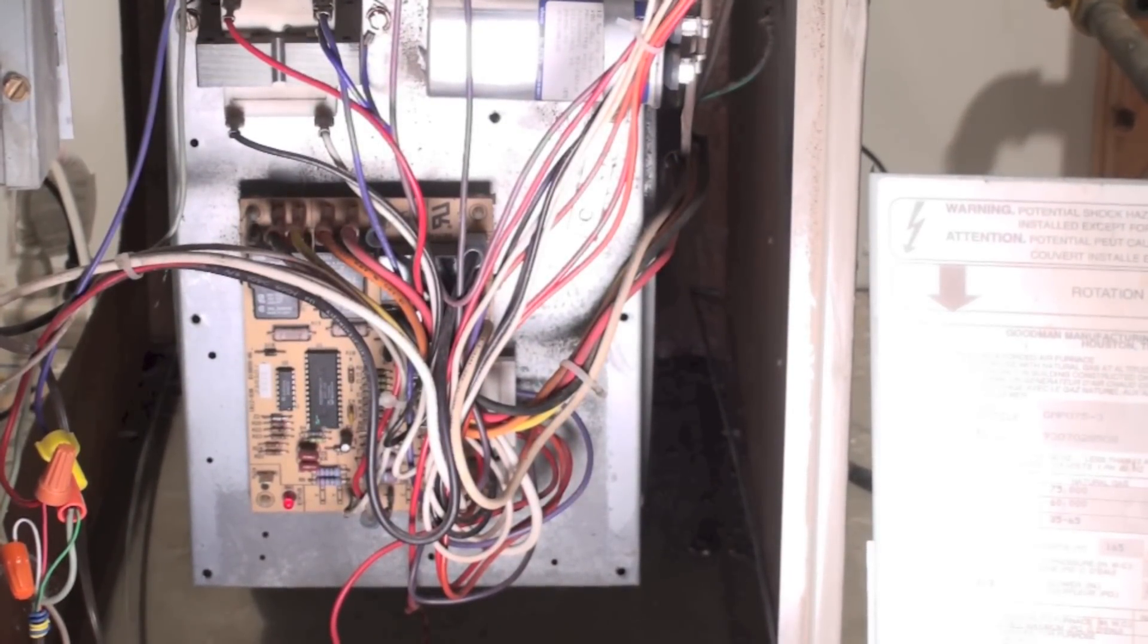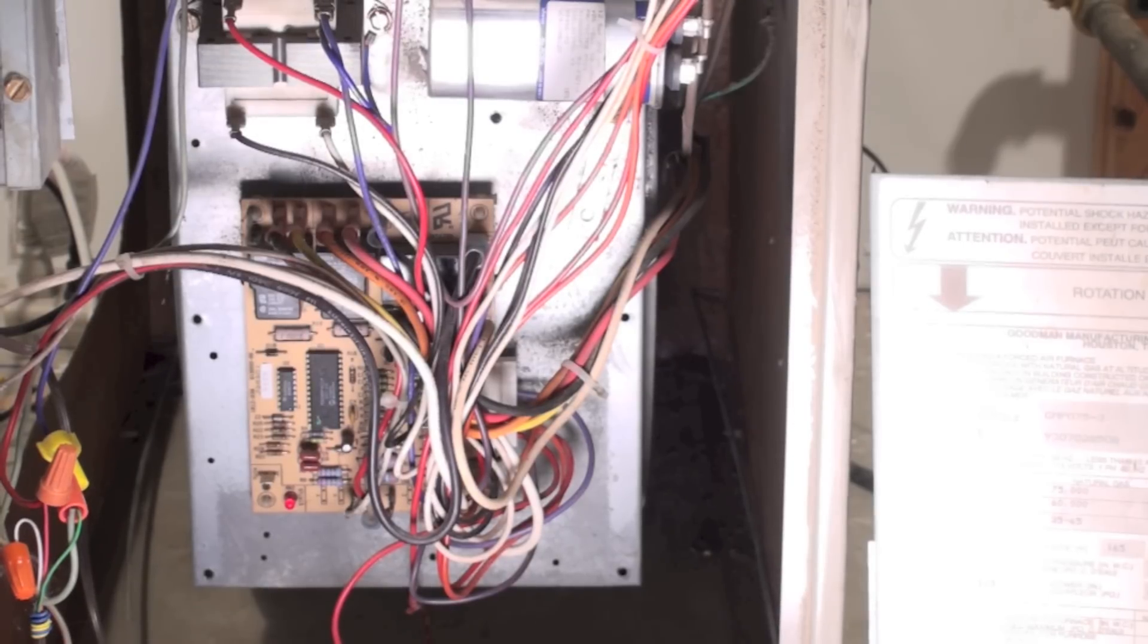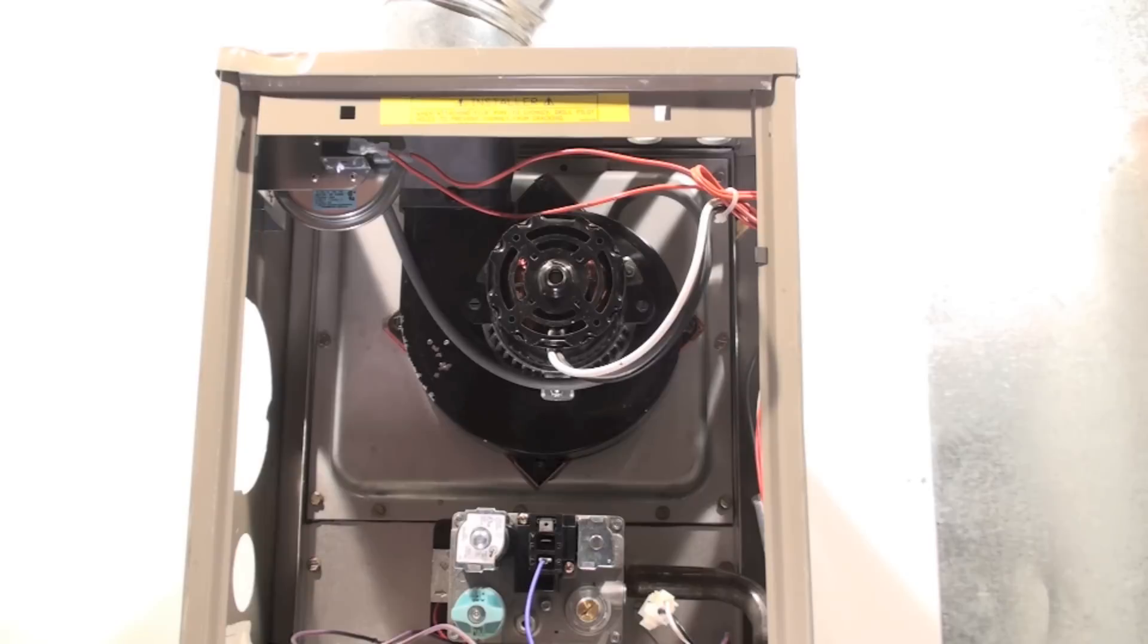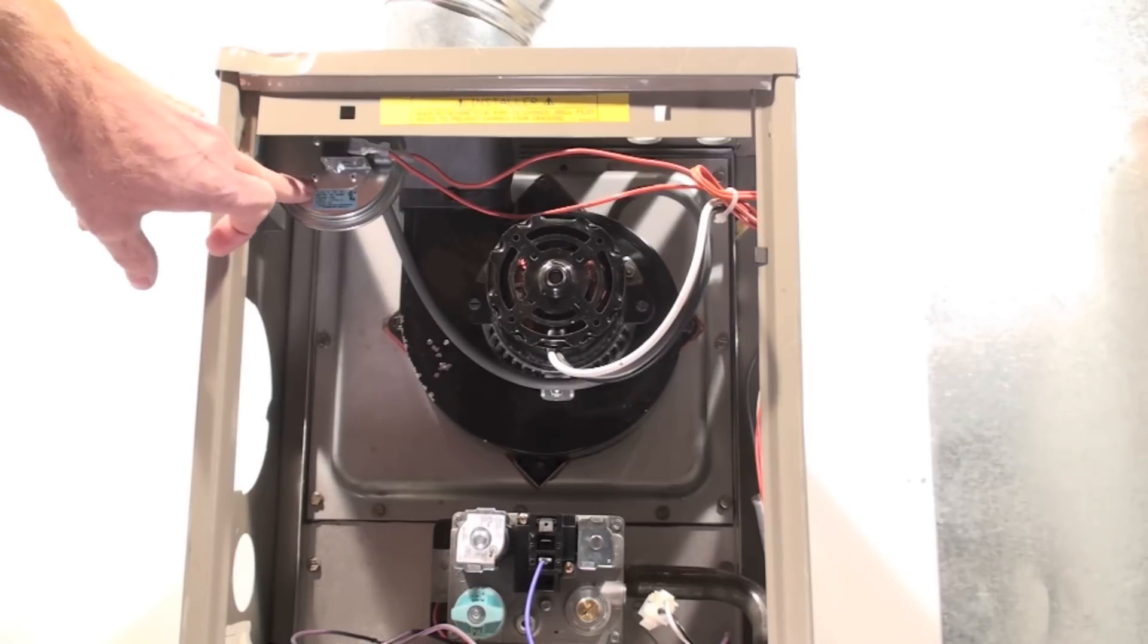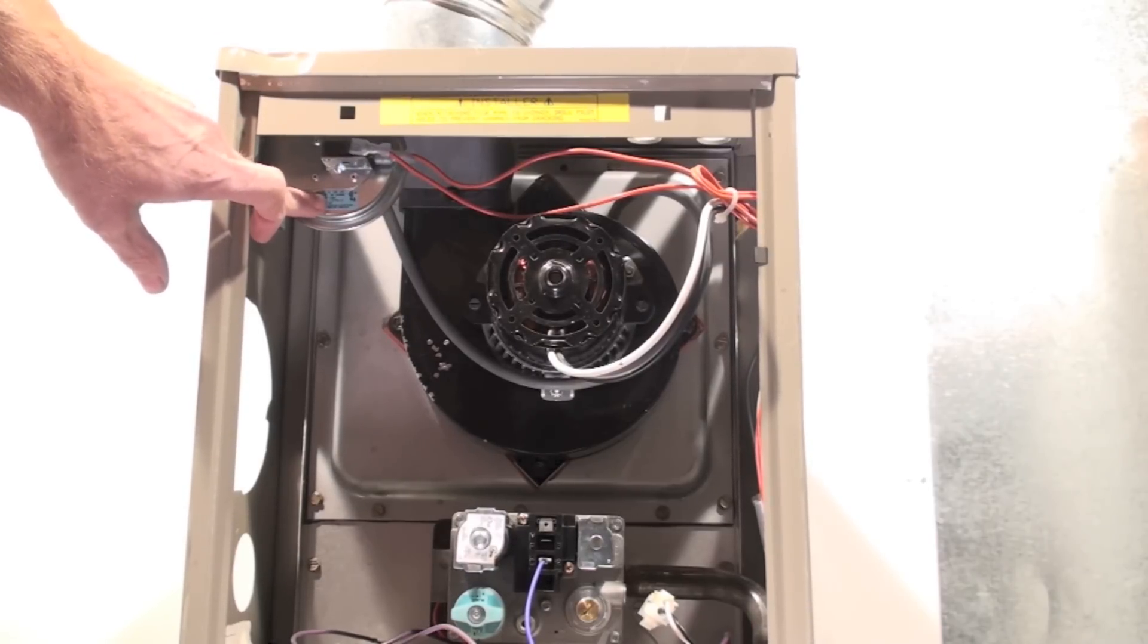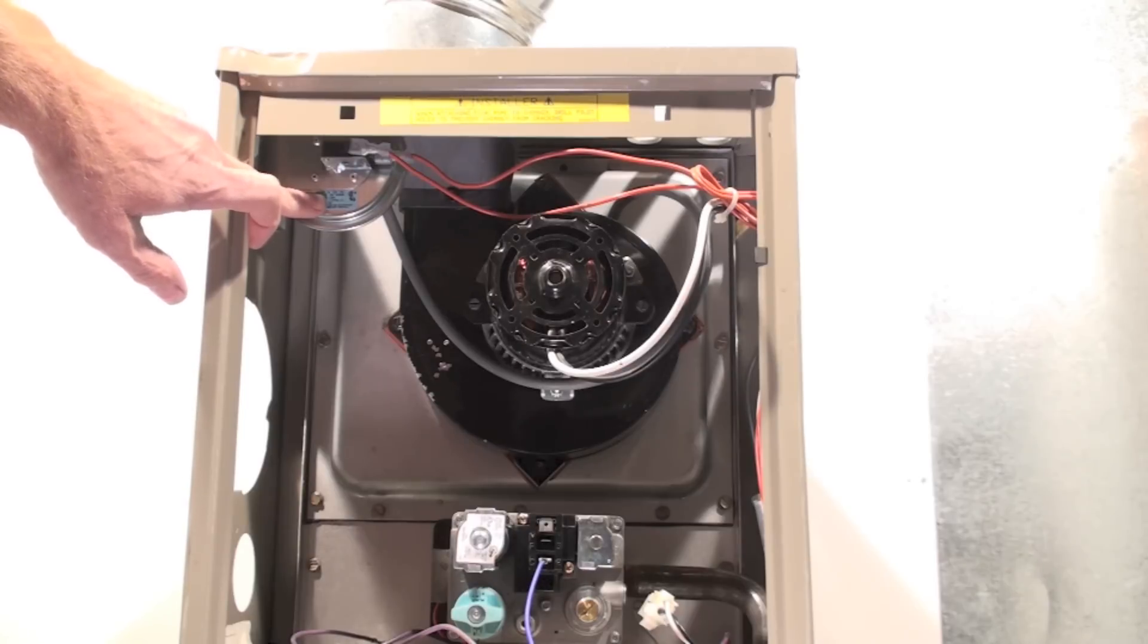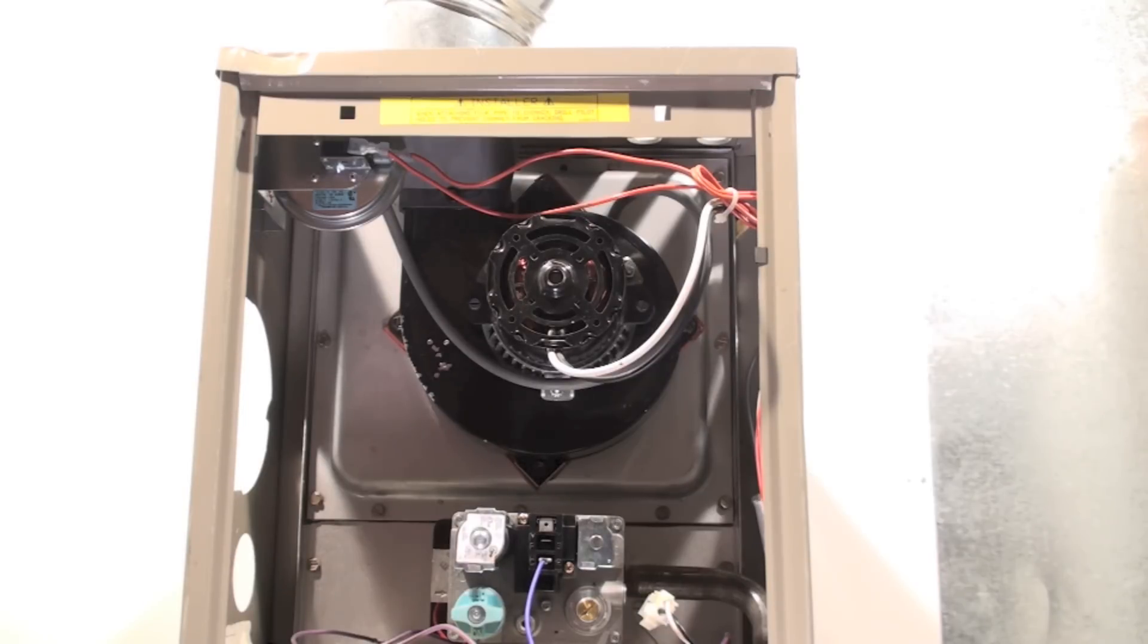Now we're going to start the cycle of this furnace. On a call for heat, the first thing that's going to happen is the IFC is going to look at the pressure switch electrically and see if it's open or closed. If it's open, then it will turn on the inducer. Now I'm going to give this thing a call for heat—I can hear that inducer come on.